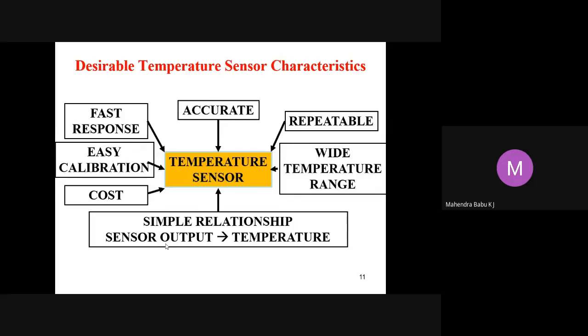The desirable temperature sensor characteristics include, first, a wide temperature range. The temperature range of a sensor defines the temperature at which the sensor is rated to operate safely and provide accurate measurement. Each type of sensor has a specified temperature range based on the property of the material.